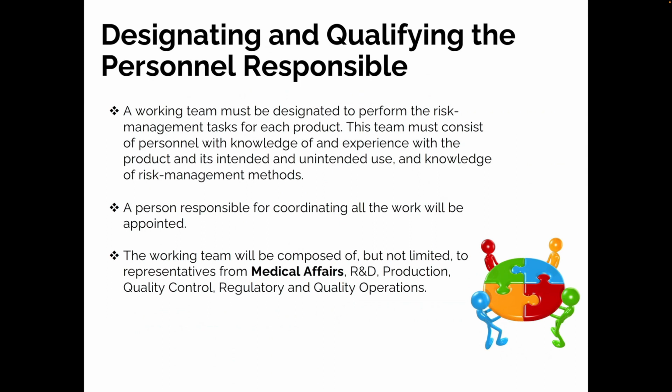So to take a step back, in terms of how you assess risk within organizations, especially healthcare organizations, there is a requirement at the very beginning. You designate who is responsible for that, and you make sure that they are appropriately qualified. You will need a working team responsible for the risk management aspects of the product development. They must contain people who are knowledgeable and experienced in the product, but also experienced in its end use, in how it's used in the field. Also, how it could be used correctly, but also what is known as unintended use, in terms of using the product in a way that you really shouldn't, but that you could predict somebody could do, in terms of misusing the product.